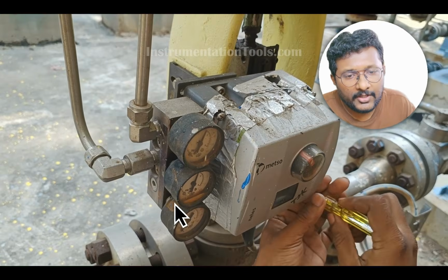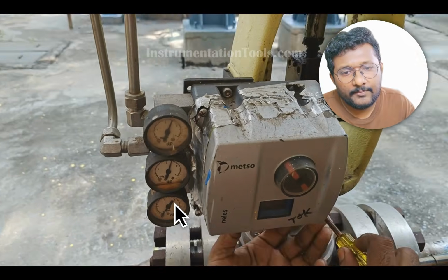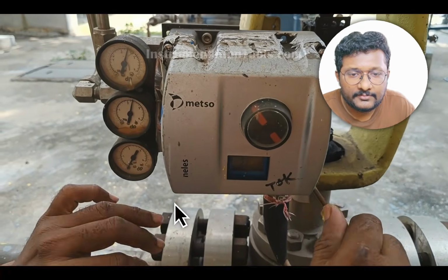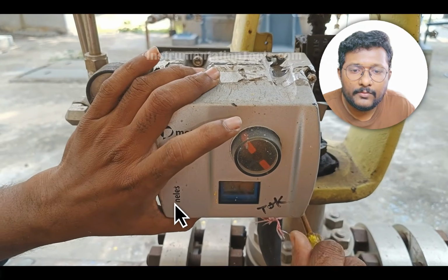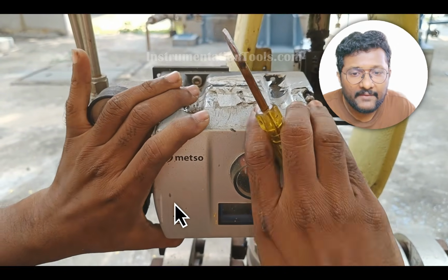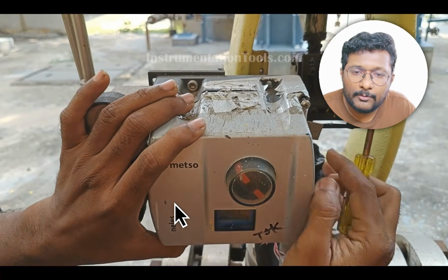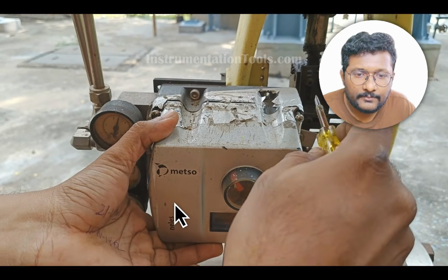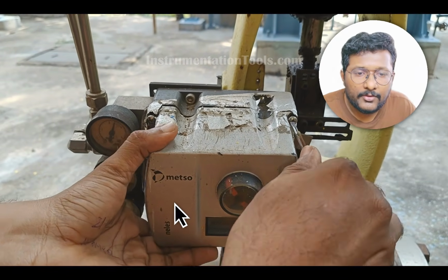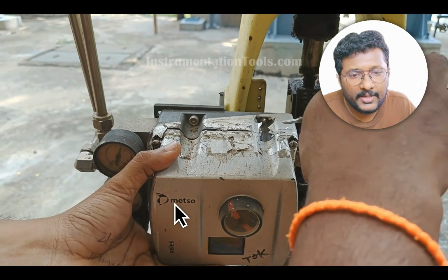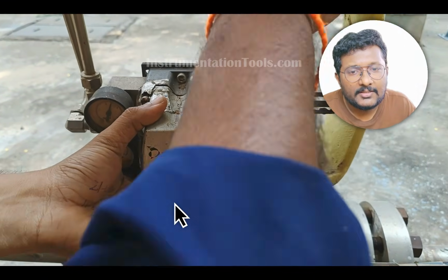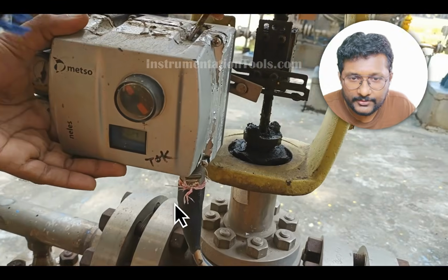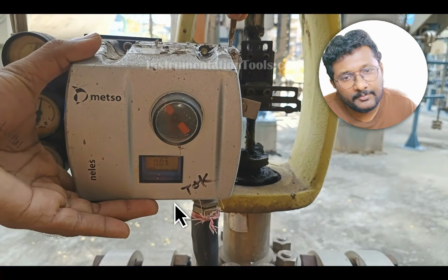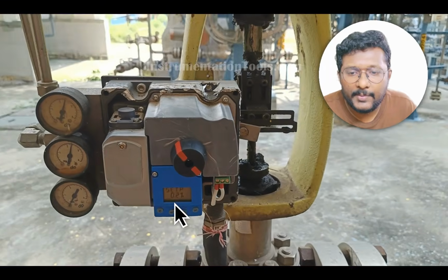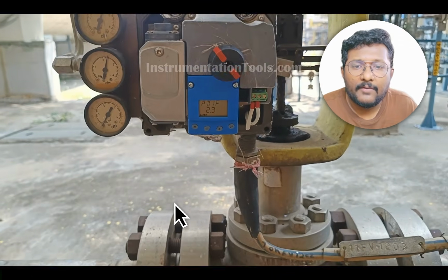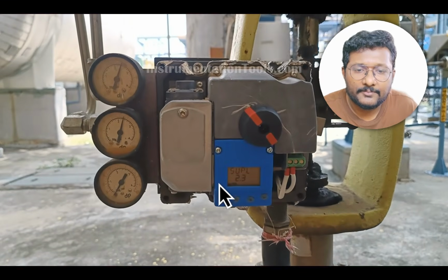Okay. You can also connect your HART communicator and you can do the same function. But in some models, we have a valve display available on the valve positioner itself. Remember, you can do the calibration using this display such that it will save some time for you. The HART communicator takes time. Remember that. That is why we prefer calibration from this small display.